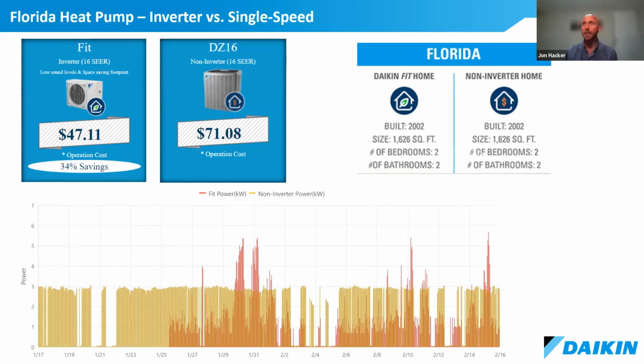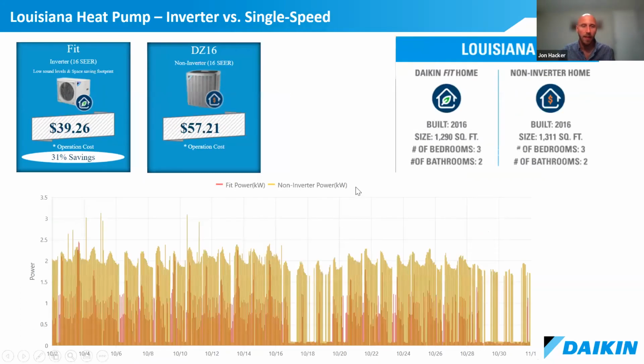And as I suggested earlier, those seasonal efficiency metrics like SEER really don't do a great job of differentiating the efficiency of an inverter product versus a non-inverter product. And we've got a couple of examples to show that here. So same thing, different location. This is a Louisiana heat pump, same systems, one inverter, one non-inverter. And the graphs are showing the same thing. We've got modulation in the inverter product, much less variability in the energy consumption of the non-inverter product.